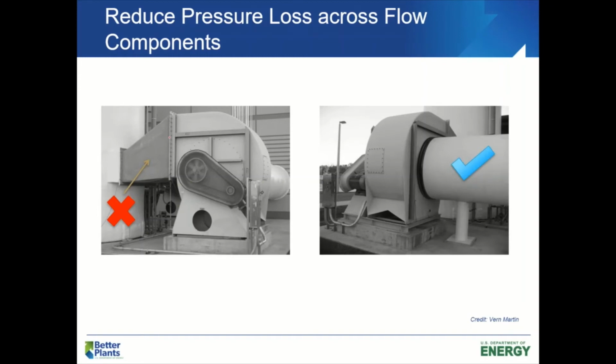So on the left-hand side here, you can see immediately, we're moving air through our fan, and immediately we're reducing that flow rate. And what makes matters a little bit worse even here is that when fans come out and are pumping a lot of air, the pressure profile really looks something a little bit like this, where almost all the air is being shoved out of the top. And in this case, we're cramming, bashing, smashing, and really constricting the ability of that fan to deliver and perform, such as the manufacturer had initially intended and designed it for. So poor configurations, poor design can really hamper or hinder what you're trying to do in a system.